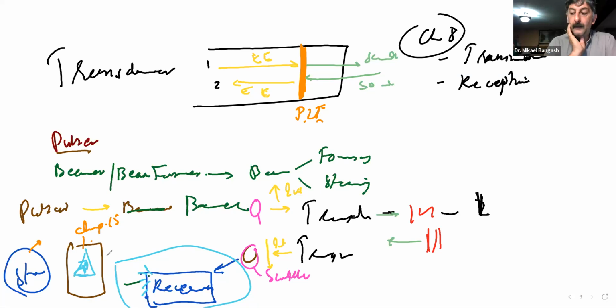So although, as your book says, pulser and beamer come after the transducer, we can mainly say, systematically, that it is the pulser and the beamer that work first to send out pulses, or pulses of electrical signals, to the transducer. And they also determine things such as focusing and steering of the beam. That's all going to be controlled by the beamer. What your transducer does is convert that electrical signal into sound during transmission, and sound back into electrical signal during reception.